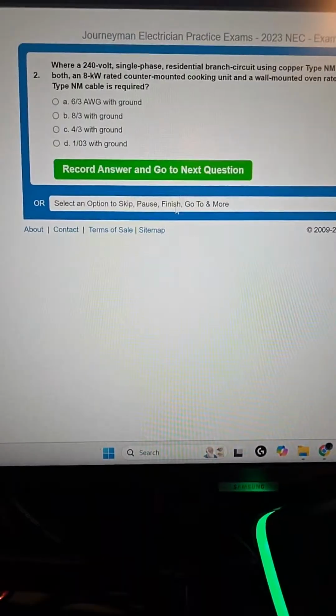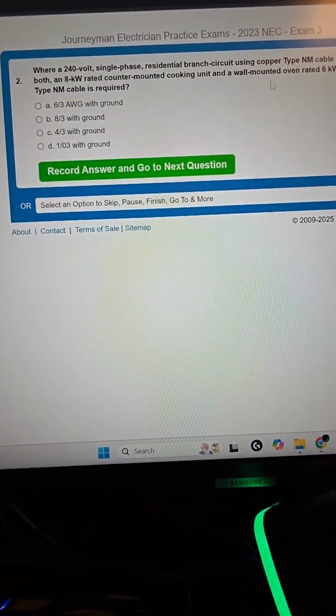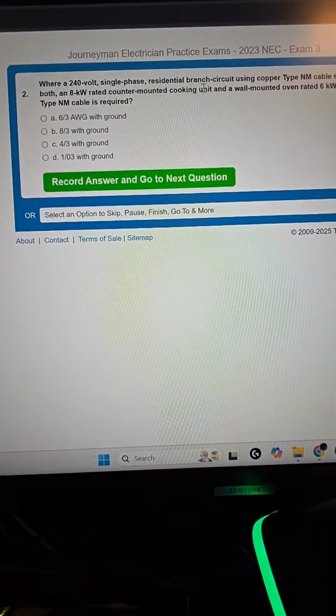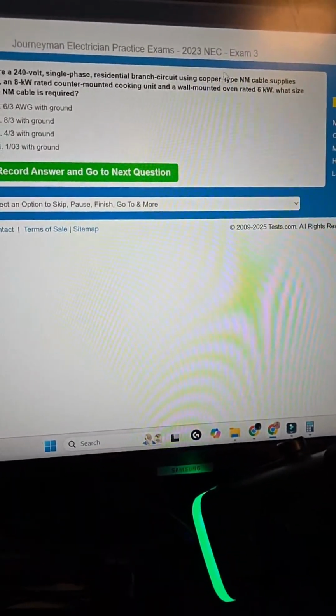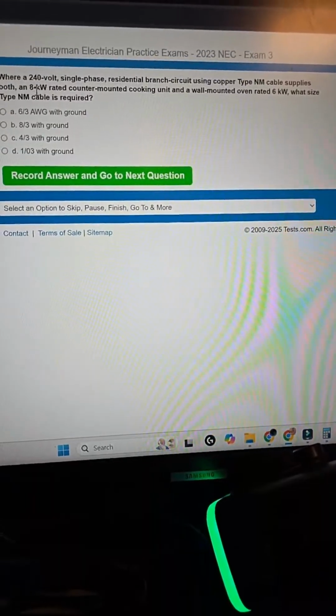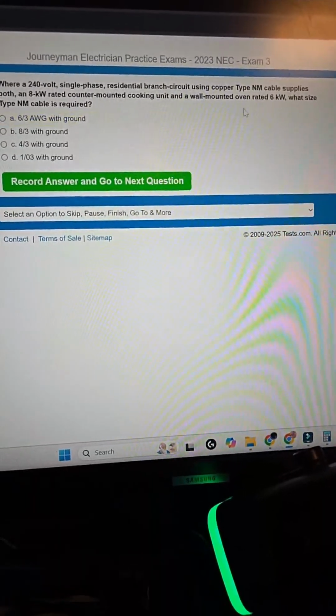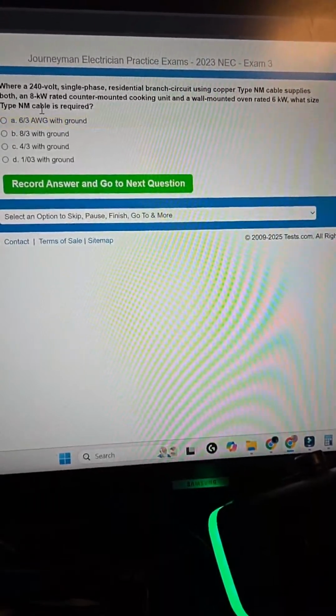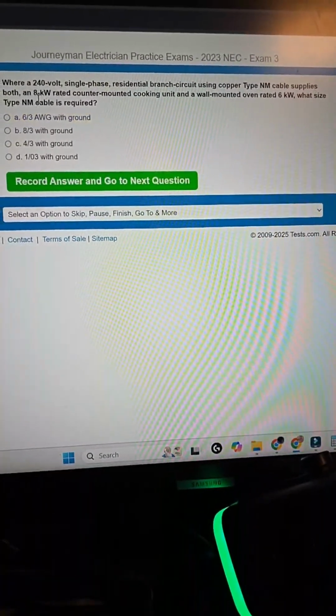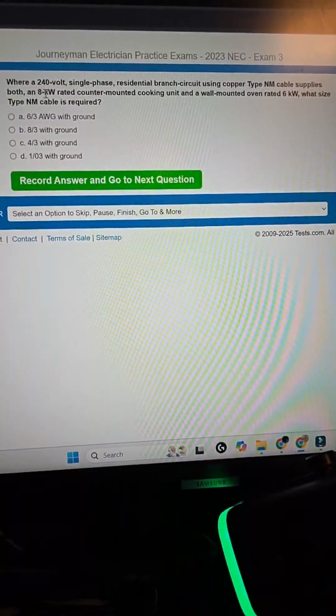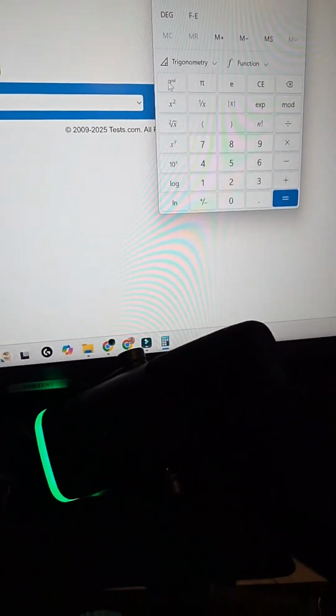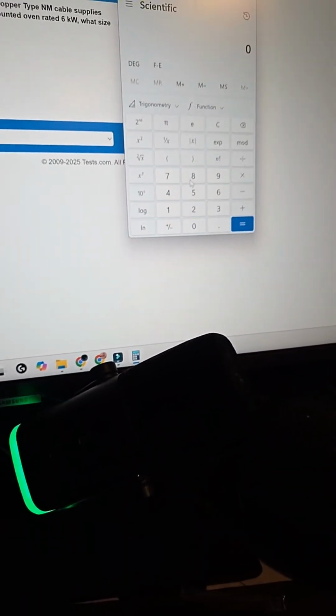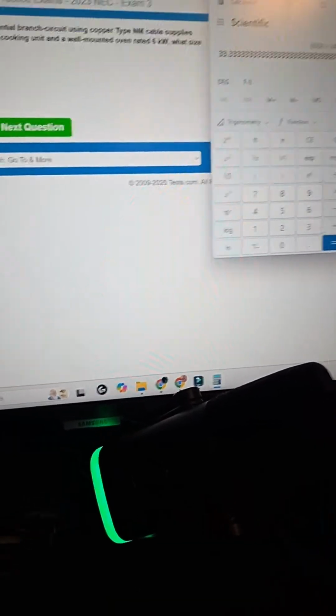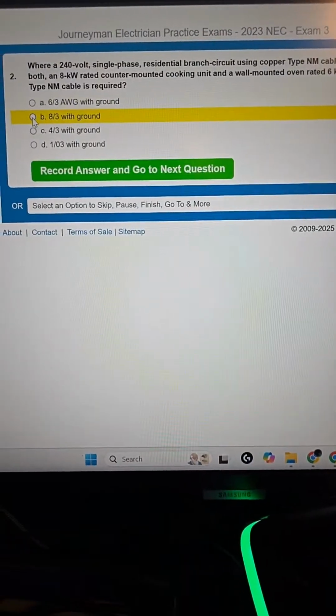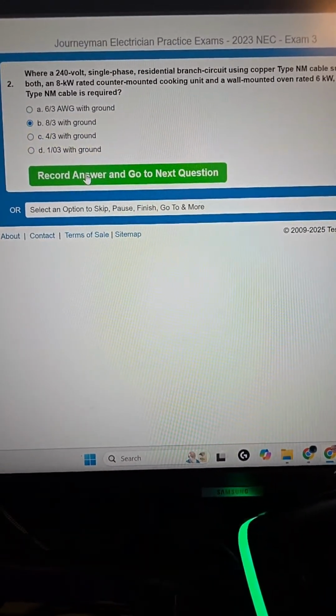Got it. Okay. A 240 volt circuit. We're just going to have to guess this. I don't have time to do this. It's NM, so it's going to be 60 degree C cable. 240 volt circuit, 8,000 watts. What size cable, based on 8,000 divided by 240? We're just gonna fudge this. I'm not gonna bother looking in the book. 8,000 divided by 240 is 33. I would say number 8-3 with a ground. That makes me nervous.